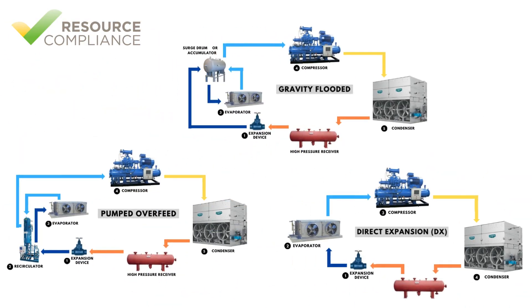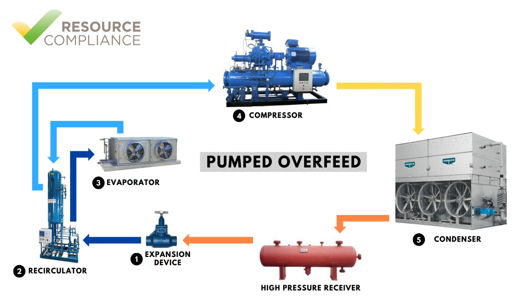As with the DX and flooded systems, the liquid will boil inside the evaporator. Vapor formed in the evaporator is returned to the recirculator, where it is separated from the liquid and rises to the top of the vessel. The vapor from the recirculator is piped to the suction inlet of the compressor.